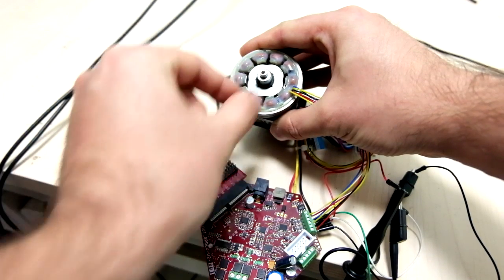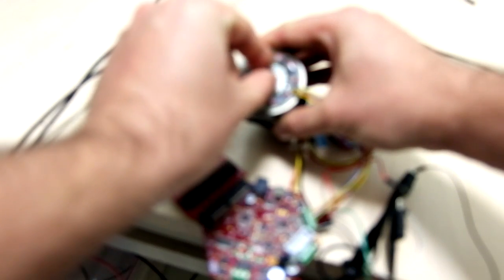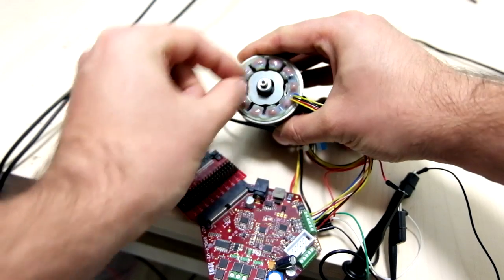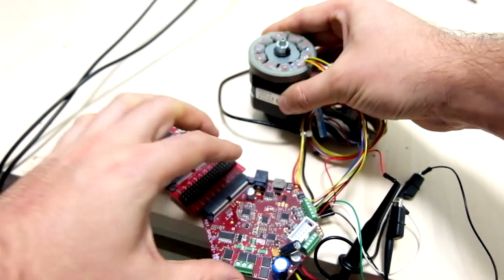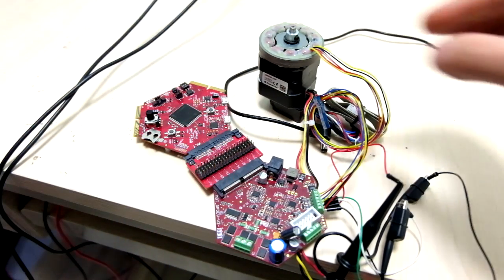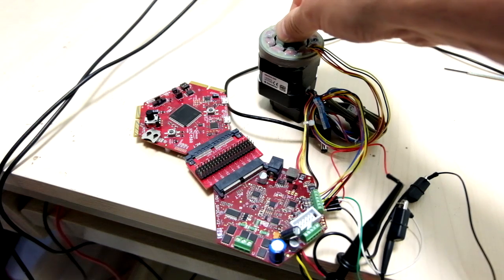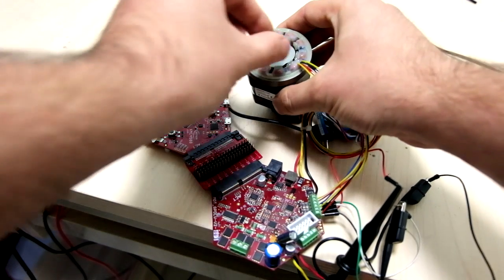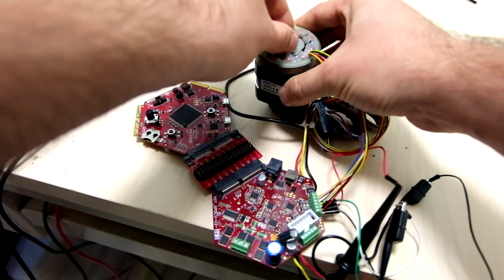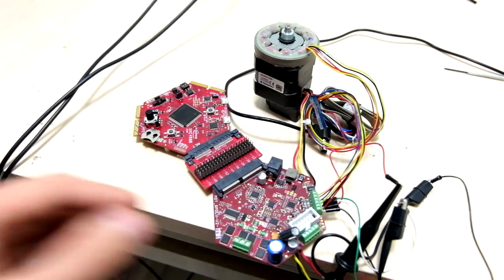there is a difference in angle between those signals, sine and cosine, and the controller board is reading that signal, the difference between the signals. In this way it can know where is the actual position of the rotor. I connected the 2 probes of the oscilloscope here.